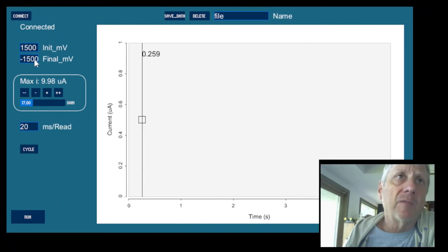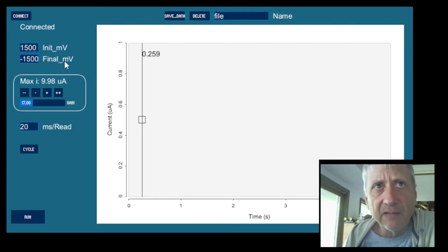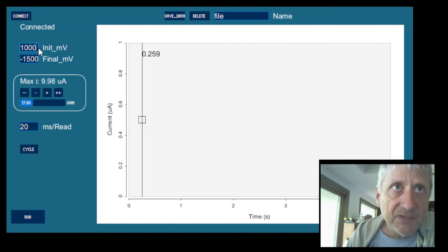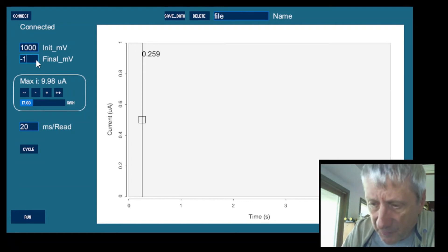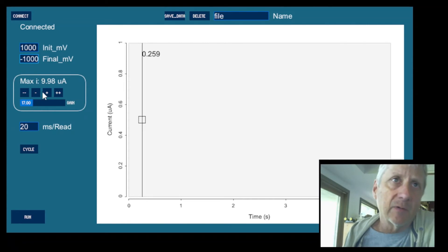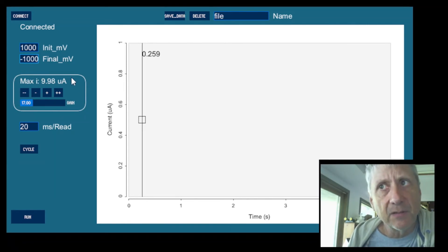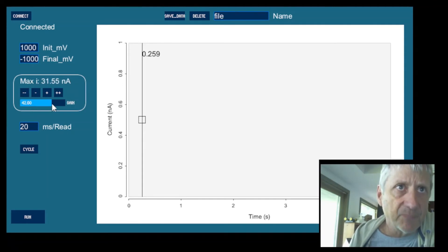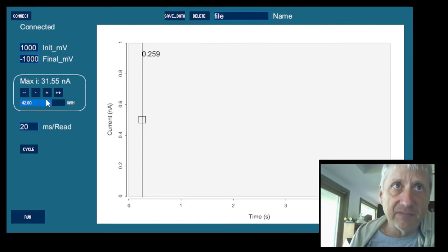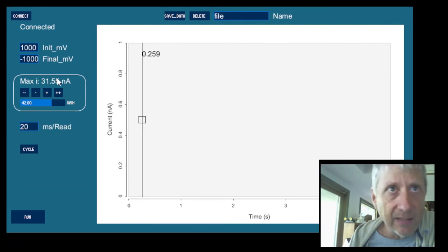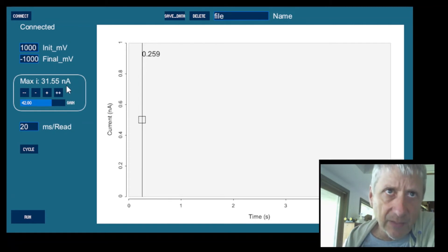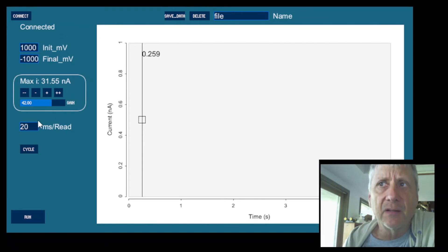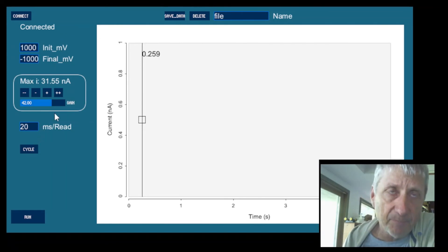Over here, you'll see two different voltages. We have an initial number of millivolts. We have a final number of millivolts. These numbers can be changed. So if you want to say 1,000 instead of 1,500, you can do that. Let's back that up and say that's 1,000 as well. Down here, we're going to specify the gain, and everything in this little box over here has to do with the gain. This slider bar, you can move it. The higher the gain value, the more sensitive the instrument is. At this 42 value of the gain, it has 31 nanoamps full scale, either plus or minus 31 nanoamps. So what you're going to want to do is adjust this depending on the amount of current that you're seeing in your experiment.